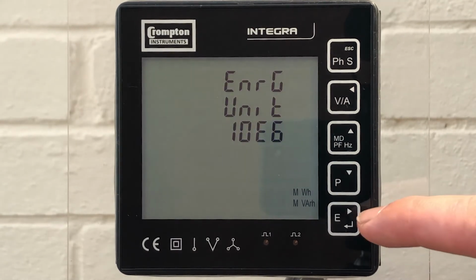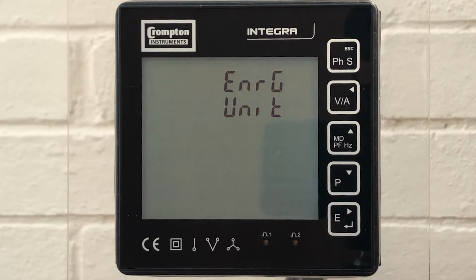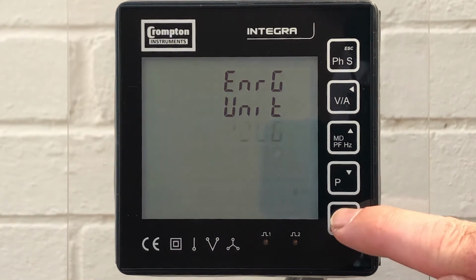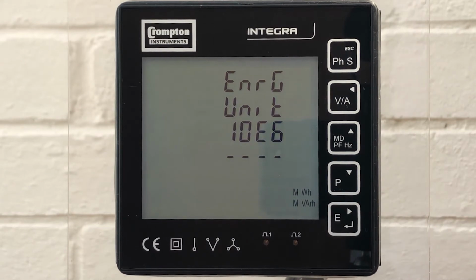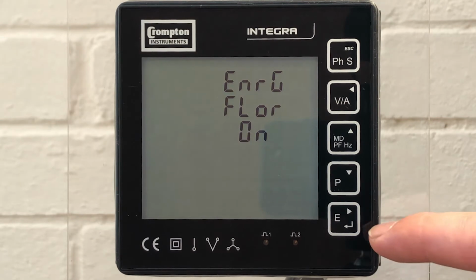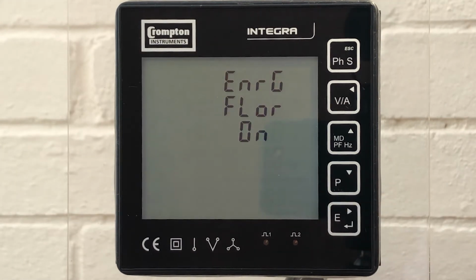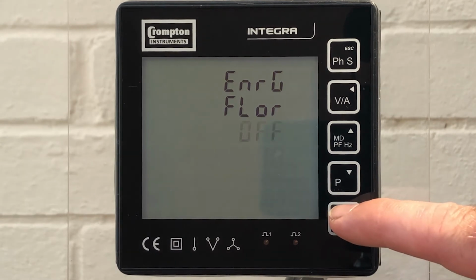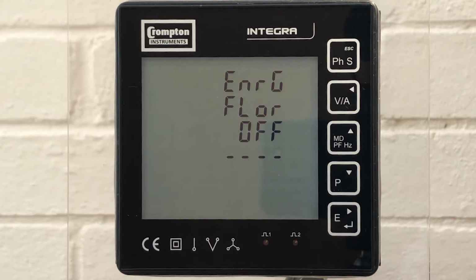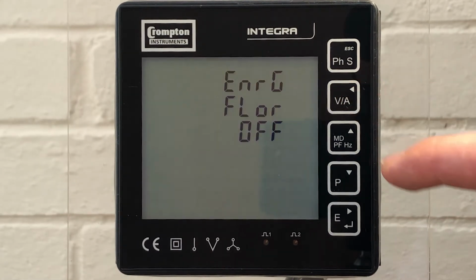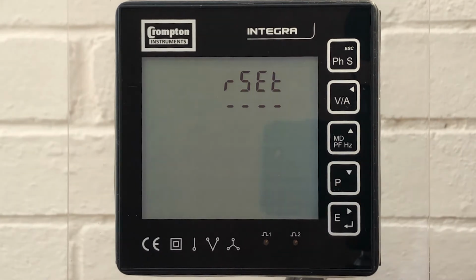This is to set the energy units used by the meter, and the available options are kilowatts and megawatts. The available units may be restricted by Integra depending on the voltage transformer and current transformer ratios programmed. The next setting is the energy floor on or off. This is to prevent creep caused by electrical noise being accumulated as energy. In the event of this being turned on, the product will employ a low power limit below which the energy will not be accumulated in the meter. We're going to set ours off at the current time.